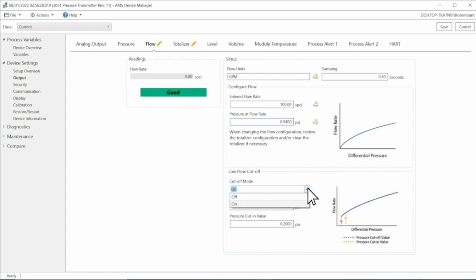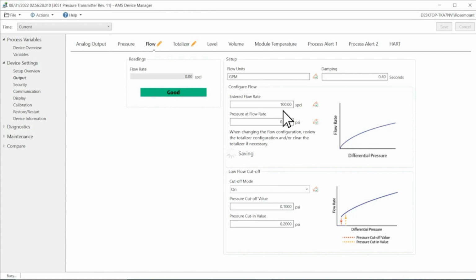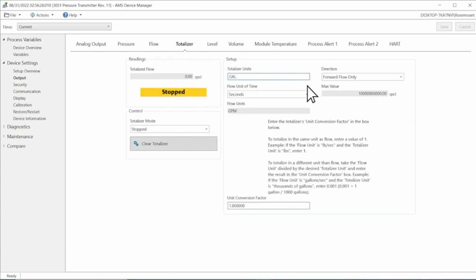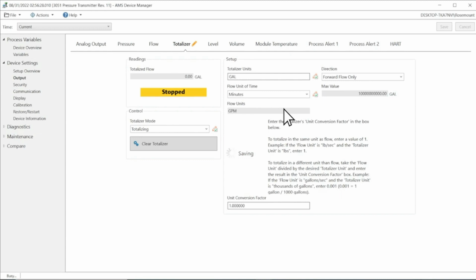Low flow cutoff is defaulted to on to prevent problems caused by process noise in low flow conditions. Damping can be adjusted on this screen as well. Select Save to implement configuration. Once flow is implemented, you can optionally configure the totalizer from the Totalizer menu. To finish configuration, the flow rate and/or totalizer should be set as output variables.